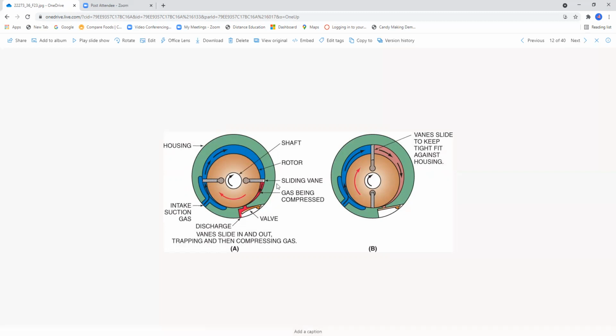We also have a sliding vane valve here. When these things break, typically these things quit pumping altogether. Then, of course, you have your discharge vanes over here, your discharge valve, and the refrigerant exits this compressor.